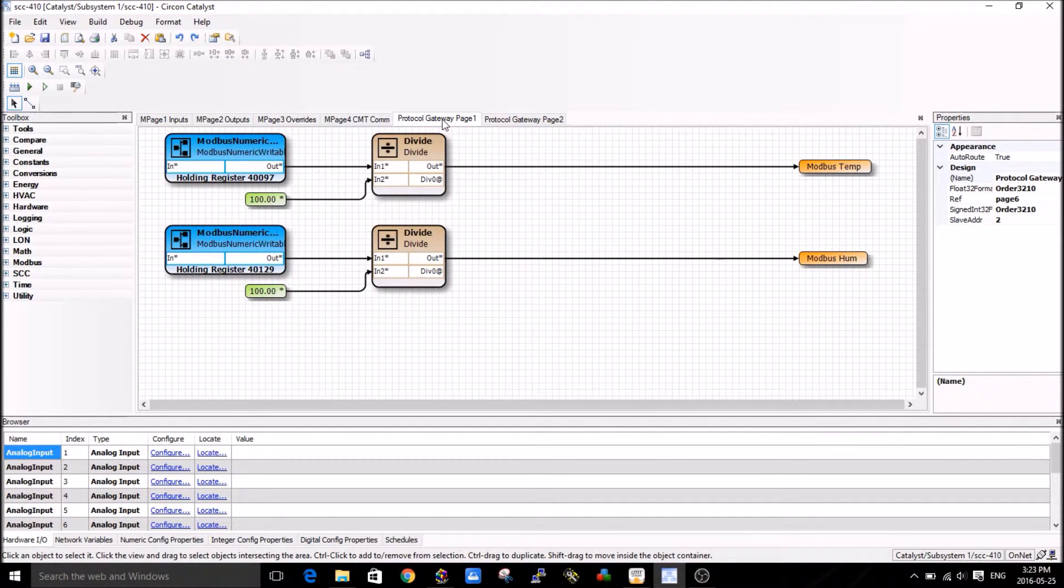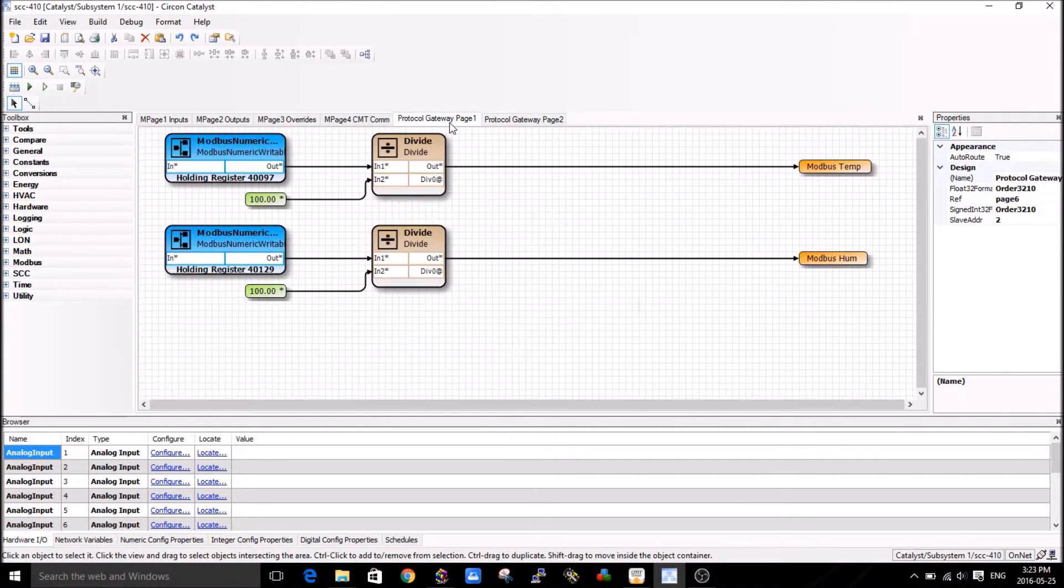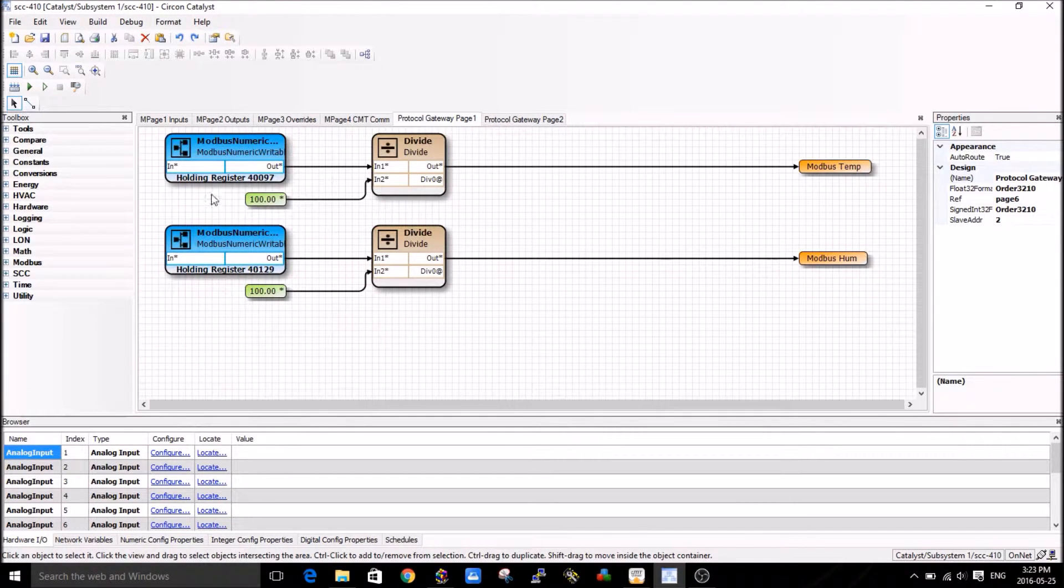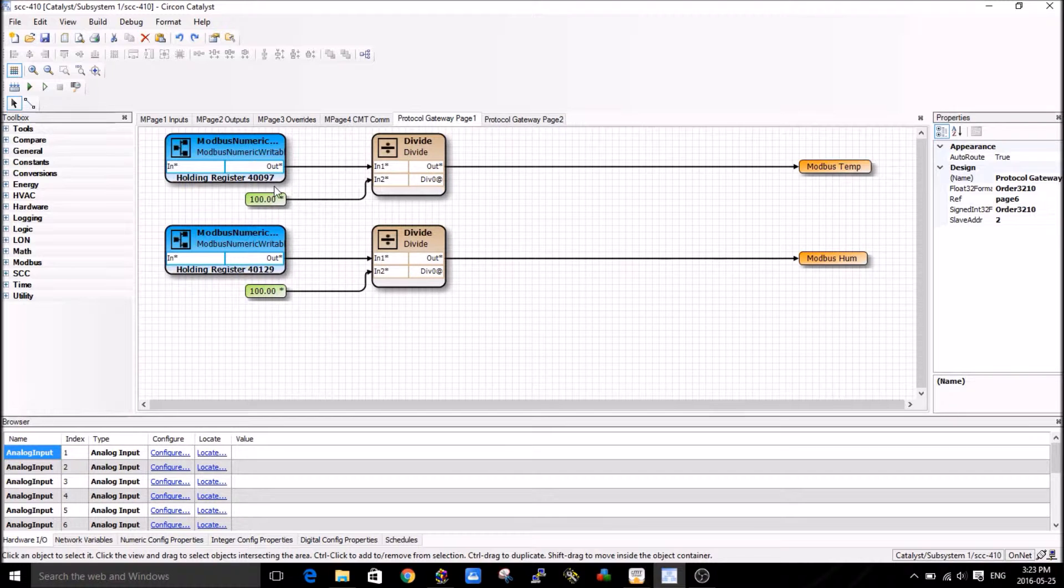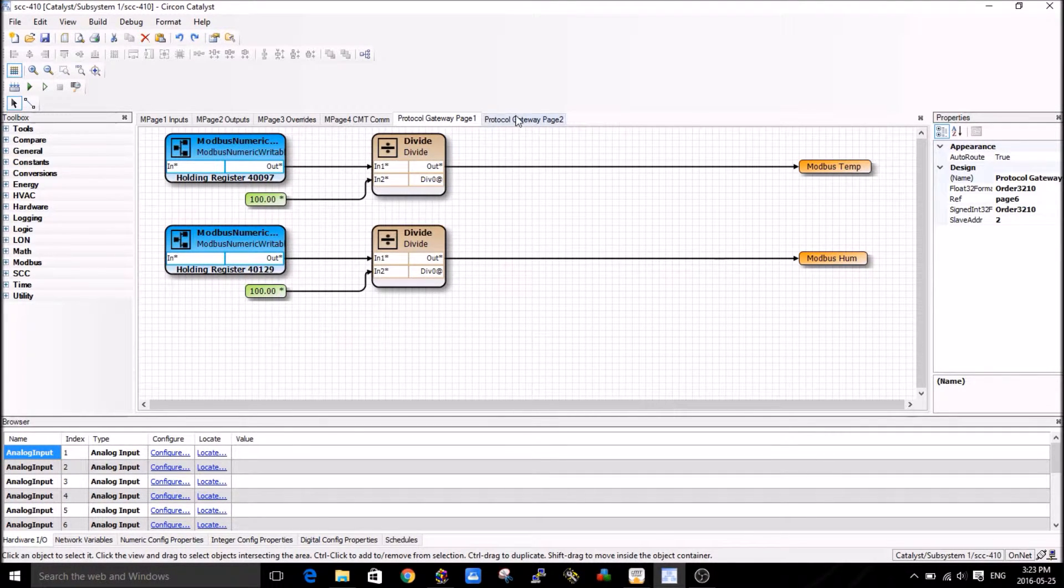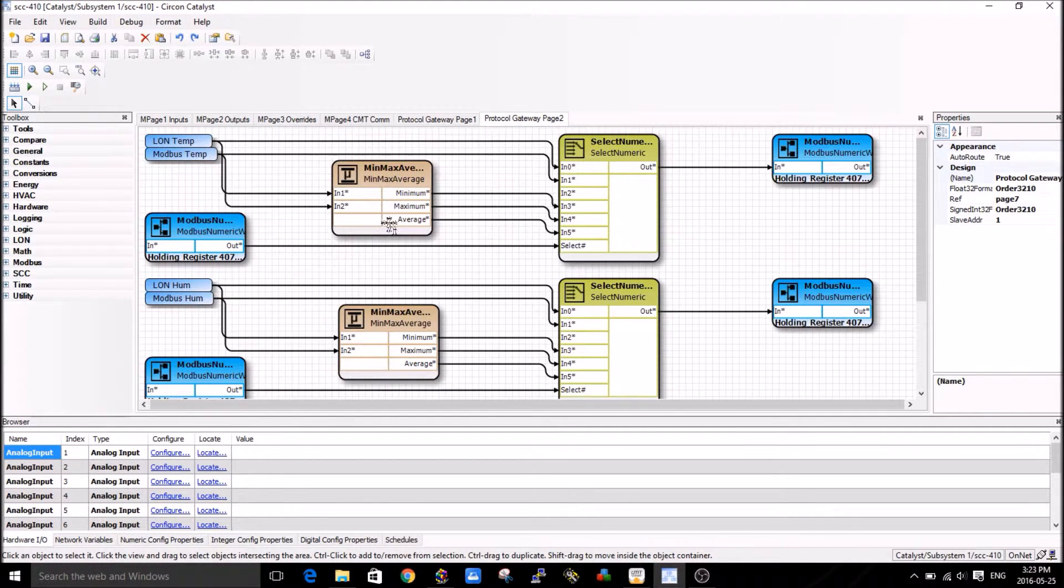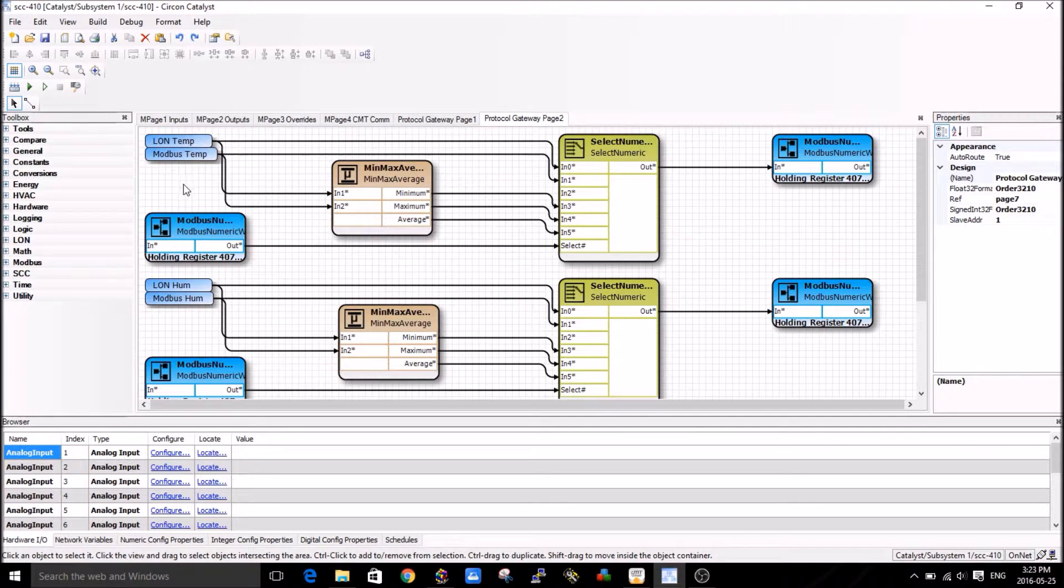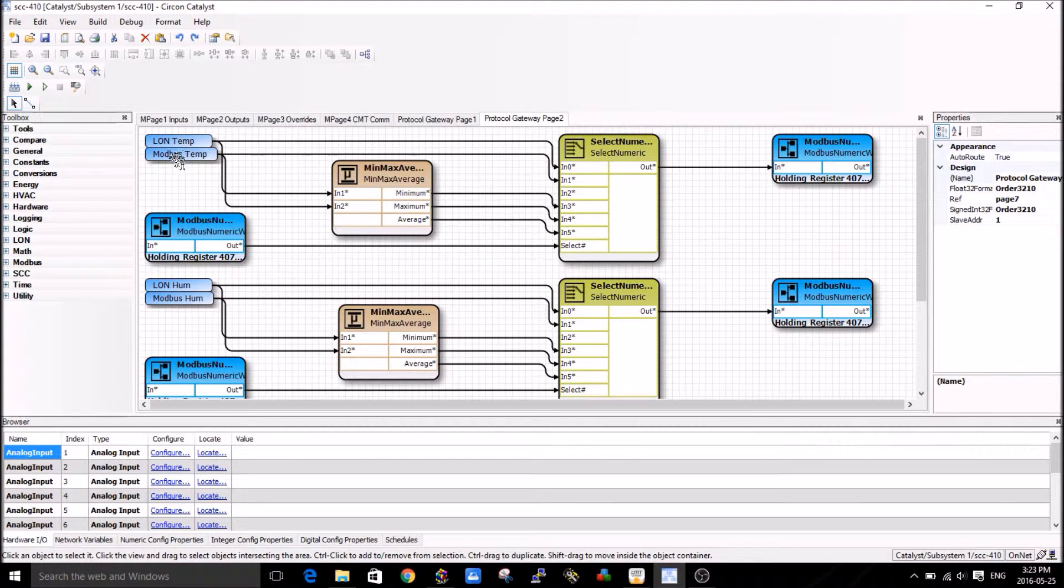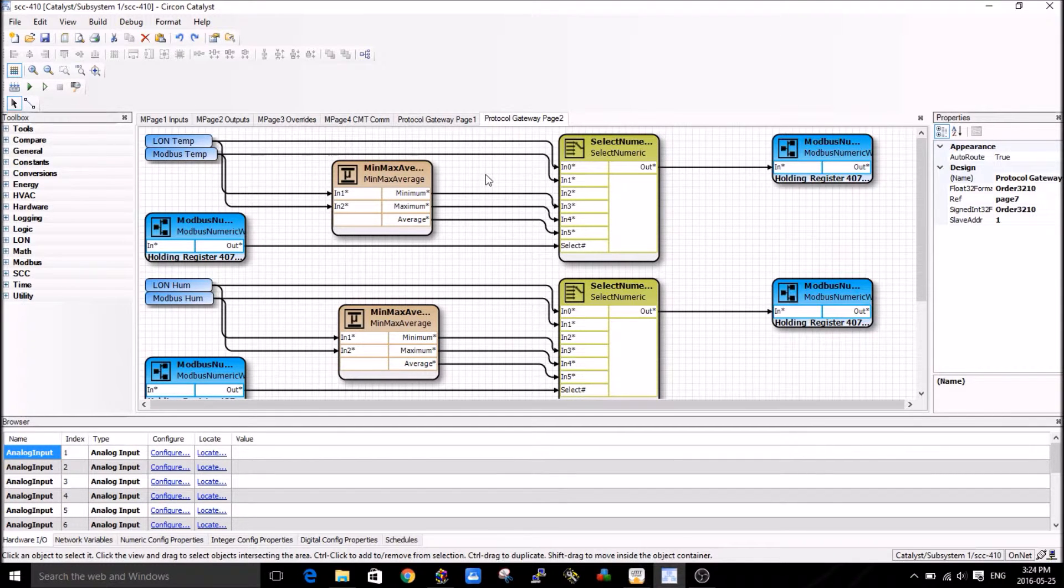The last two pages are my gateway blocks that I've done, gateway functionality data. I have two pages where I read some information. For example, in this one I'm reading information from the Modbus sensor and I'm dividing it by 100. In this page I'm doing a min, max, average on the data between the LON sensor as well as the Modbus sensor, and I'm sending it to a third system which in this case is my display.